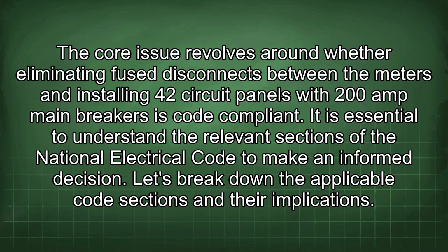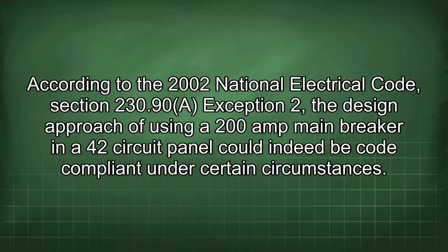It is essential to understand the relevant sections of the National Electrical Code to make an informed decision. Let's break down the applicable code sections and their implications. According to the 2002 National Electrical Code, Section 230.90 Exception 2, the design approach of using a 200 amp main breaker in a 42 circuit panel could indeed be code compliant under certain circumstances.